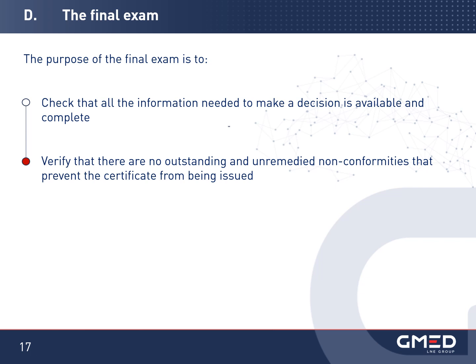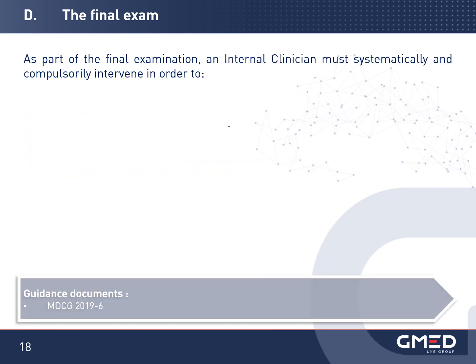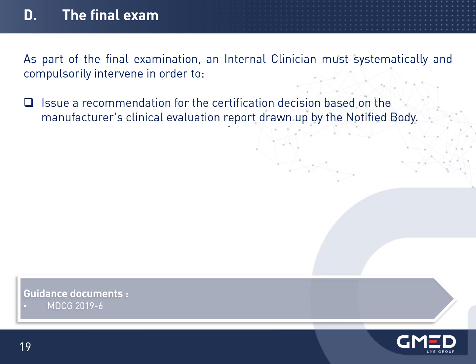It also checks that there are no outstanding non-conformities that have not been rectified and which prevent the certificate from being issued. As part of the final examination, the notified body must systematically and compulsorily call on the internal clinician to issue a recommendation for the certification decision on the basis of the manufacturer's clinical assessment report drawn up as part of the technical documentation assessment activity.